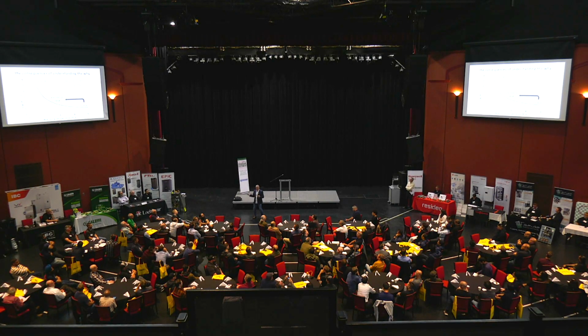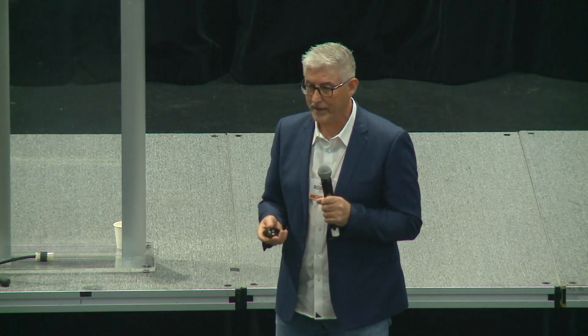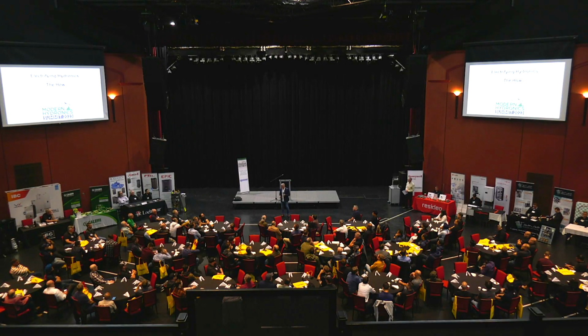So moving from typical performances from heat pumps to these low exergy systems means you have to engineer the systems. So if you're not one that gets attracted to the math, find those in the room that do the math and work with them. But don't just think you're going to get these things to do because it says it on the label or it comes in the brochure. You have to put it in. There has to be some math done in order to move it into these ranges. So that's why we need to electrify.